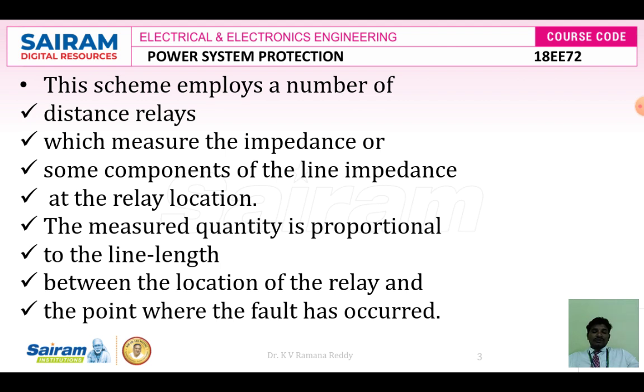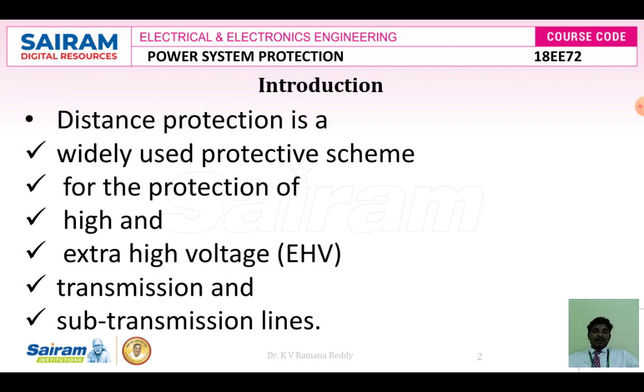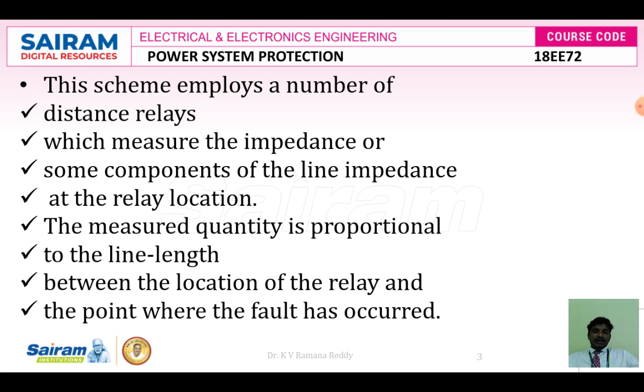From the fault location towards the relay location, if we calculate line parameters like line impedance, line admittance, and line susceptance, based on all these values we conclude whether the fault happened or it is due to a transient. Compared to overcurrent relays, distance protection gives better operation and better performance, because we are calculating the line parameters to determine whether it is a fault or a transient. Distance relays are applicable for extra high voltage, transmission line, and sub-transmission line applications.